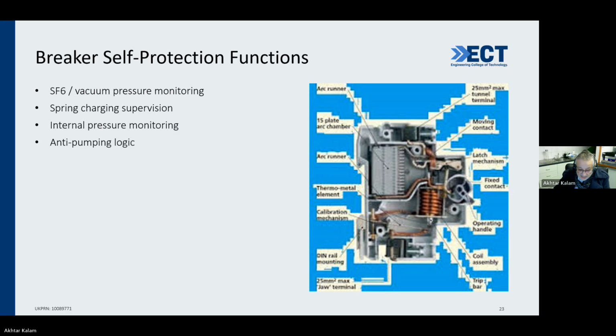So my friend, at that time, I want to go over what the breaker self-protection function does. In particular, you have heard about SF6 breakers, vacuum breakers, all sorts of breakers, which have spring charging supervision, internal pressure monitoring, and anti-pumping logic. Look at the contacts: there's a fixed contact and a moving contact, and that's how it works. So many trips occur locally by the breaker, not by the relay. It's not the poor relay which is at fault. The breaker itself has initiated the tripping.